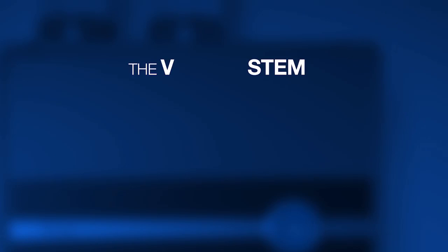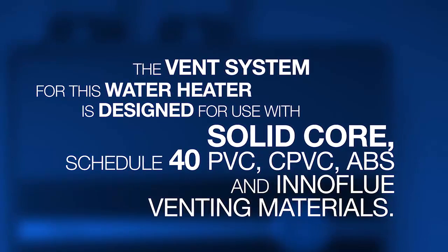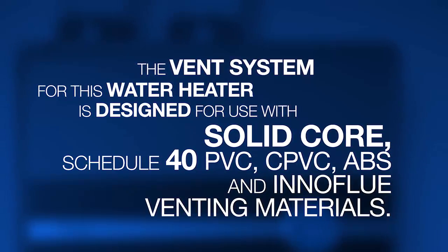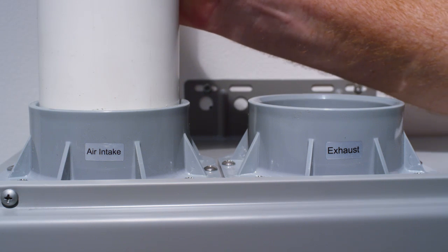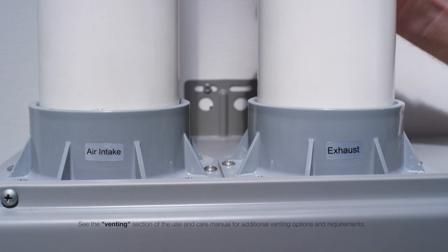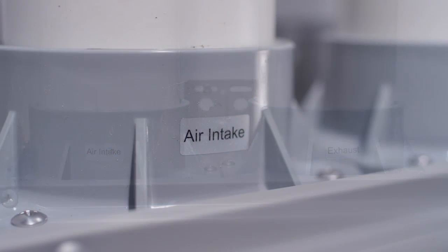Installing vent pipe. The vent system for this water heater is designed for use with solid core schedule 40 PVC, CPVC, ABS, and InnoFlue venting materials. Both the exhaust and air intake vents must be run outside. Measure, cut, and dry fit the venting together before gluing the fittings. Start at the water heater with the exhaust and work your way to the termination going outdoors. Complete the air intake as well.